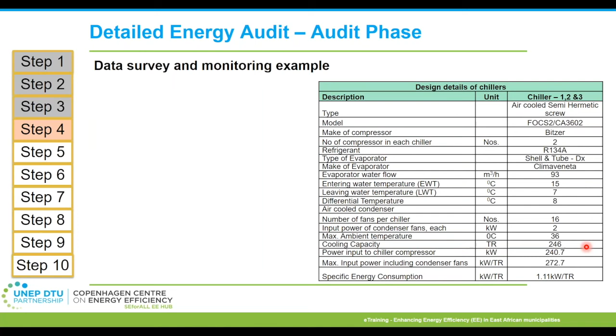Step 5: the auditing team starts conducting detailed measurements, experiments, and trials on energy-intensive areas. They monitor parameters like maximum demand, power factor, and kWh, study load variation trends, and measure and evaluate performance parameters such as pump efficiencies or heating and cooling loads, and how they vary throughout the day, process, week, or month.